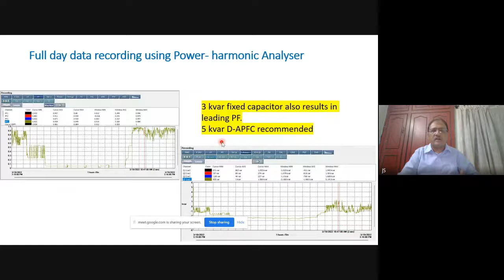So this is again a commercial industry, a commercial data center, 11 kV supply HT. They are paying 8 rupees per unit as the charges. So here, this industry had a power factor of 0.9, which they are supposed to maintain, but they maintained only 0.88. They were less by 0.02, and that cost them a penalty. So we worked with them. We worked with data of power factor as well as the harmonics. Then we came with a solution where we suggested to them a reduction of 5th order harmonic, so that the leading power factor does not happen.